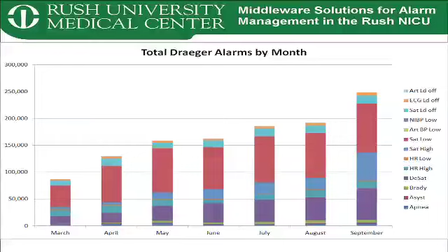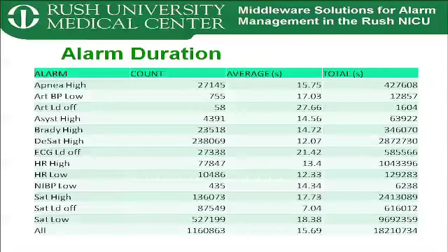If you look also at alarm duration, how long do these alarms last? Because that's also an important factor. The total is 18 million seconds. If you work that out, that's about 7 months. So what that means is, in our 7 months of continuous alarm over a 7-month period, on average in our unit, one patient was alarming at any given time. That means there are a lot of alarms going on. If you walk down the hallway, that's why you hear alarms, because there are alarms going a lot of the time.